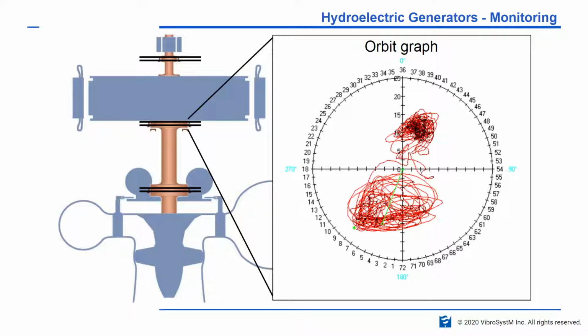We see that consistently when we analyze data, correct, Paul? Yeah. And this is easy for us to analyze. It means that the air gap is smaller in this area here prior to excitation, and when they excite, the magnetic pull is stronger there. Therefore, the unit will go in that direction. It will remain there so long as the magnetic field is present. Once the magnetic field is removed, the unit will immediately go back to its mechanical center.